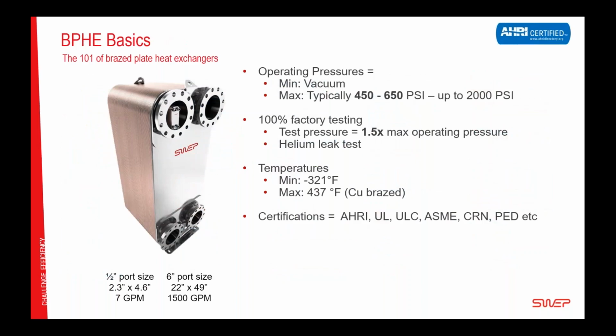One slide to explain the brazed plate heat exchanger. If we start on the top left, we have the smallest heat exchanger that SWEP produces at the time being. It's a B3. It's the size of an iPhone 4, so it's a palm size, and it's inside the 6-inch port, or 150 millimeter, of the 649, which is the biggest one we have right now. And so the SWEP range is anything from palm size to a little bit more than 5 feet tall with 6-inch ports. What combines these two heat exchangers is that the operating pressure minimum is vacuum.